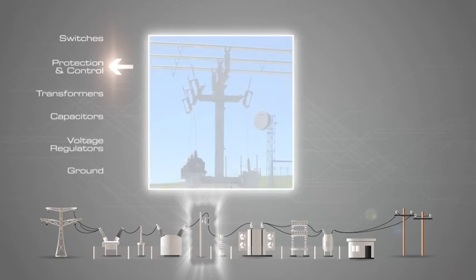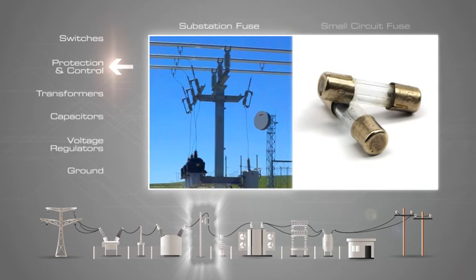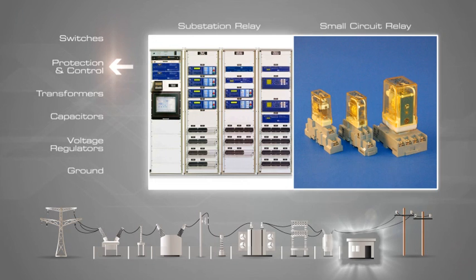An example of protection equipment is a fuse. A fuse is a type of low-resistance resistor that acts as a sacrificial device to provide overcurrent protection of either the load or source circuit. A fuse interrupts excessive current so that further damage by overheating or fire is prevented. A digital protective relay uses a microprocessor to analyze power system voltages and currents for the purpose of detection of faults in an electric power system.